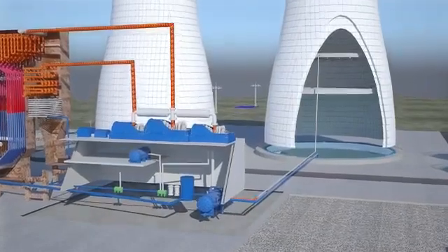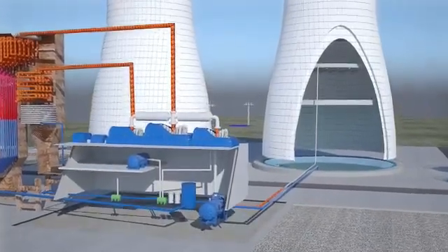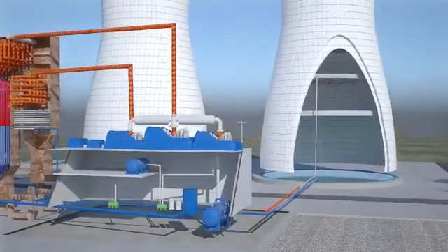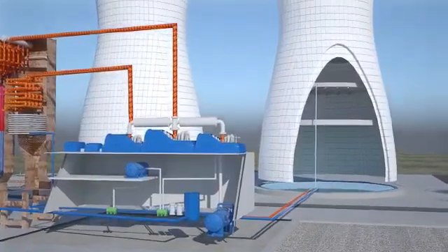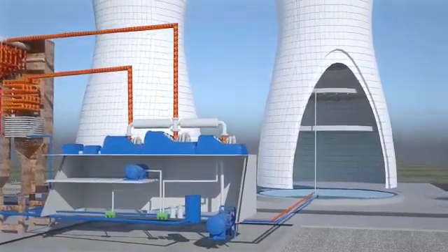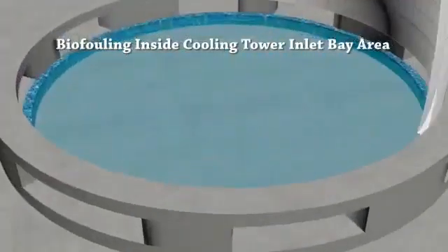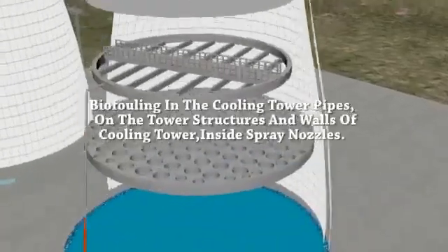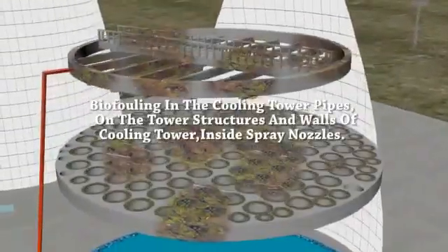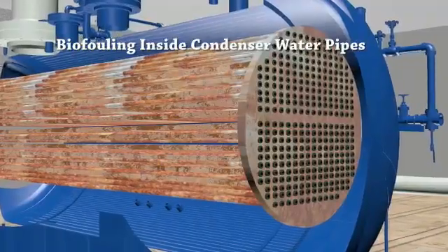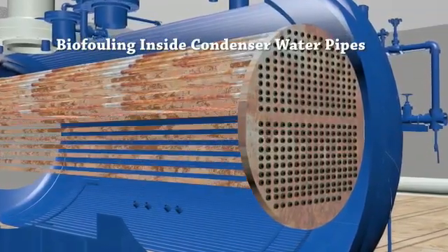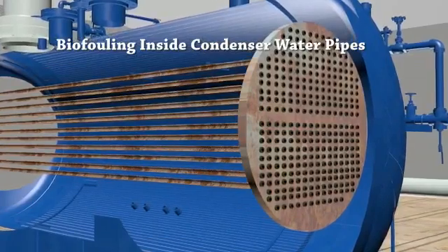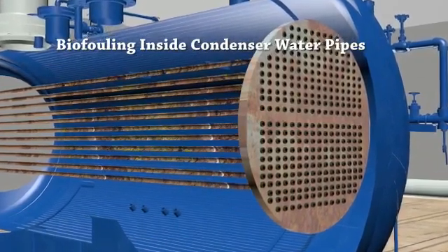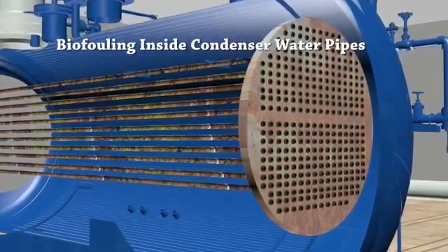The presence of TOC in cooling tower water causes biological fouling. Higher levels of TOC rapidly accelerate the biofilm formation. This further leads to formation of a biofilm in the cooling tower inlet bay area, cooling tower pipes, walls of the cooling tower, inside spray nozzles, inside condenser pipes, etc. The biofilm formation inside condenser pipes will drastically reduce the heat exchange process, leading to the inefficiency of the condenser.